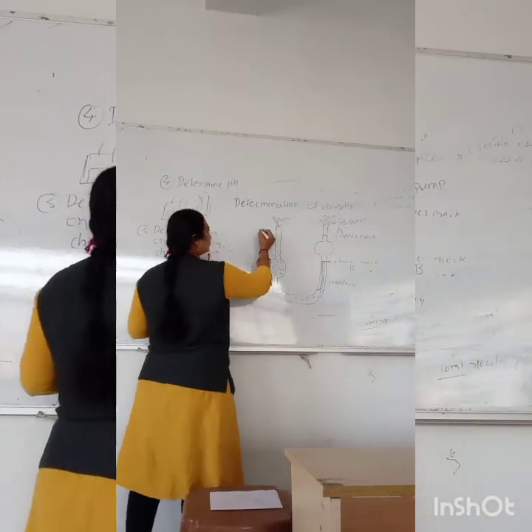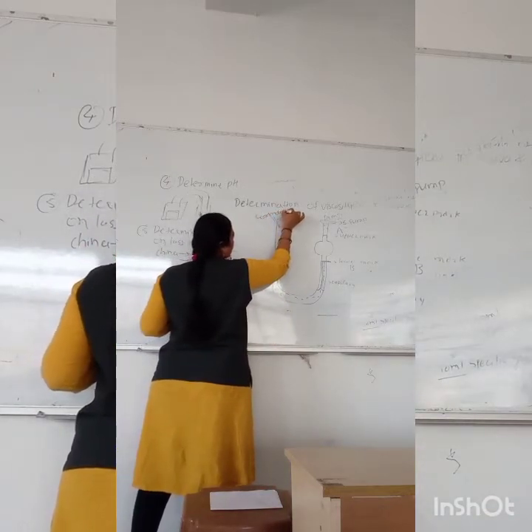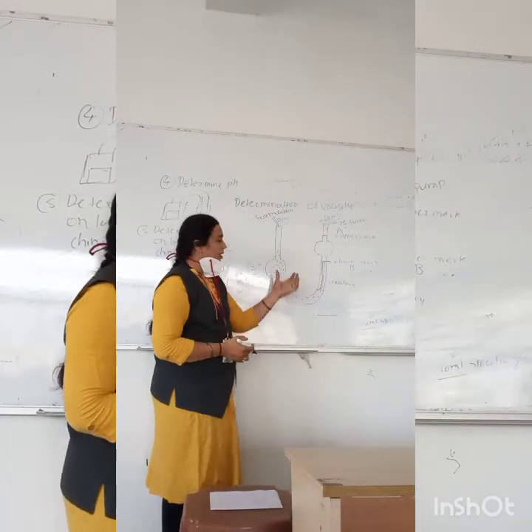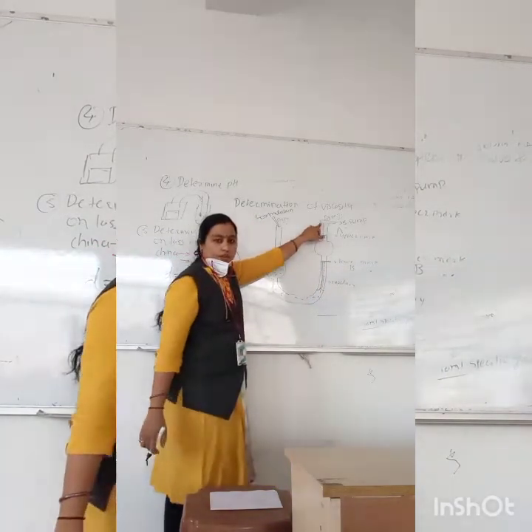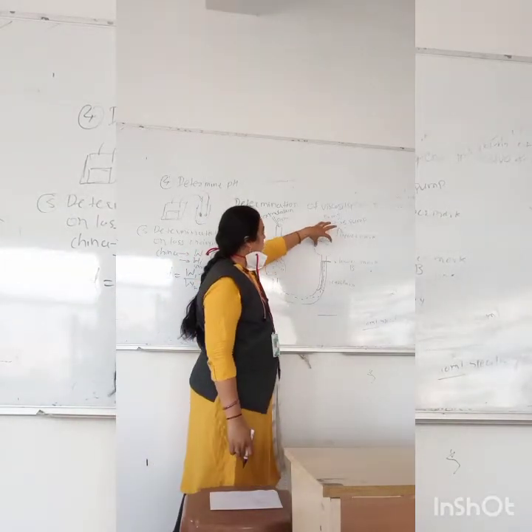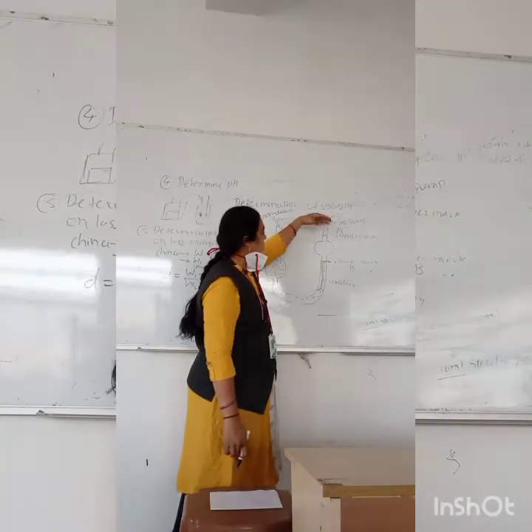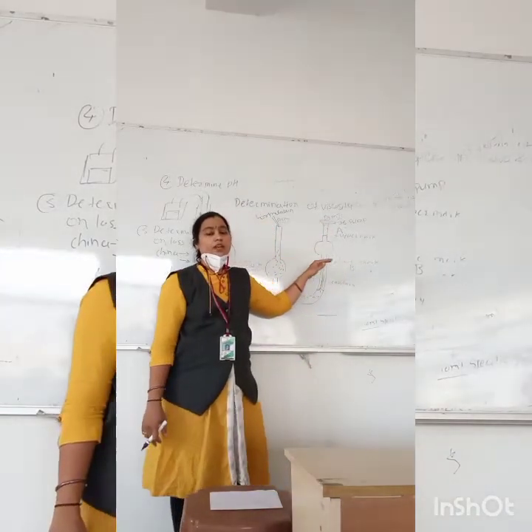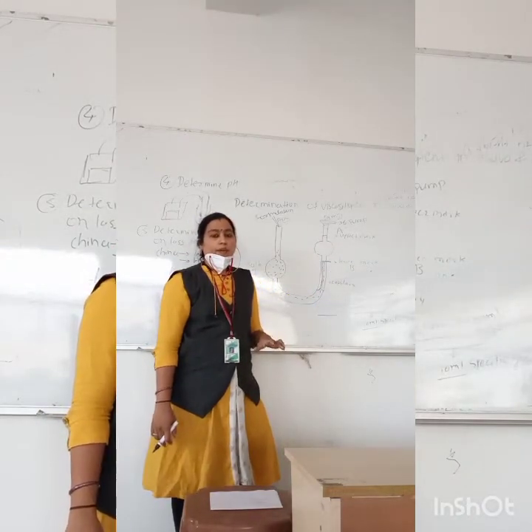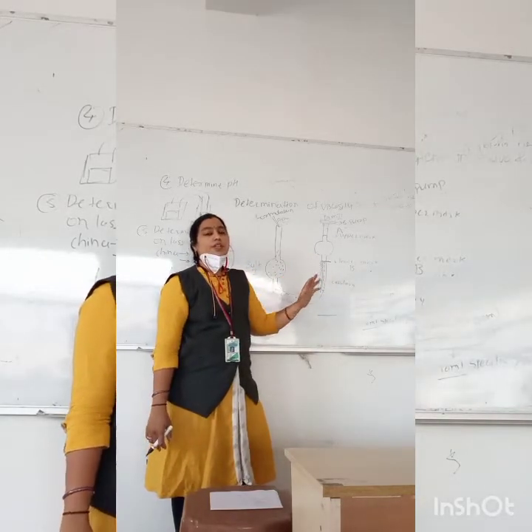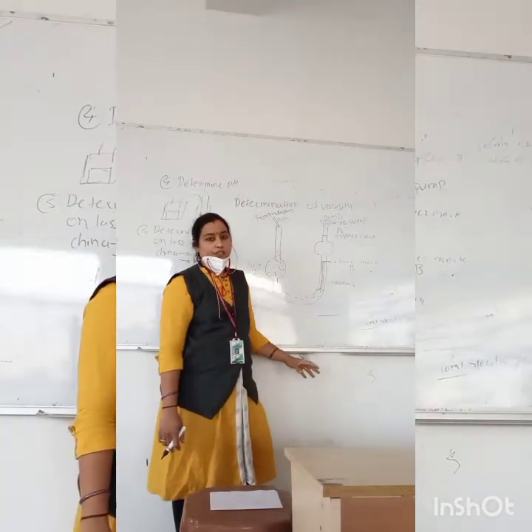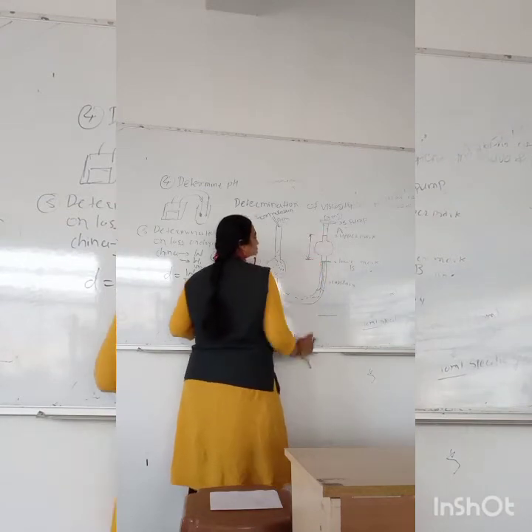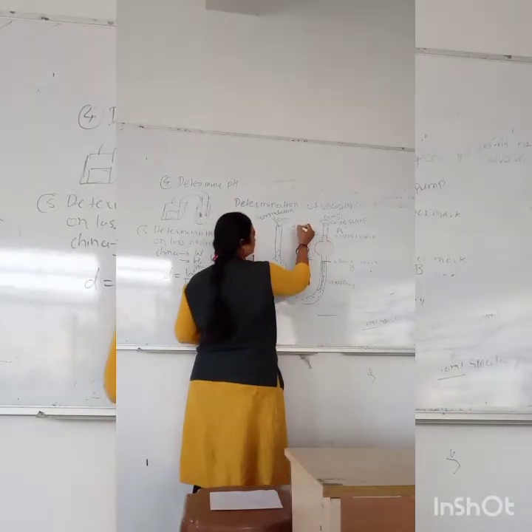Remove the distilled water from the viscometer and add the formulation. Repeat the same procedure: add suction, allow liquid to rise above mark A, then start the stopwatch when it reaches A and stop when it reaches B. You will get two readings — one for distilled water and one for the formulation — giving the time required for flow from A to B for each.